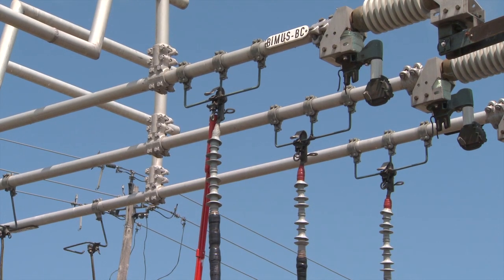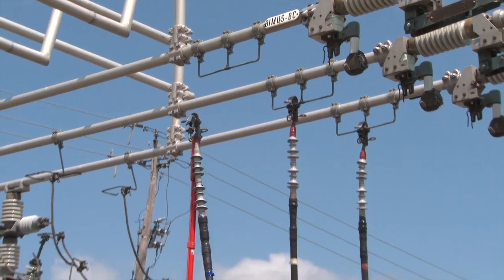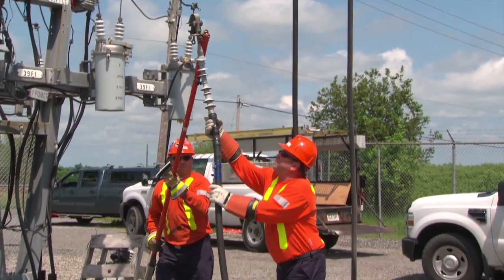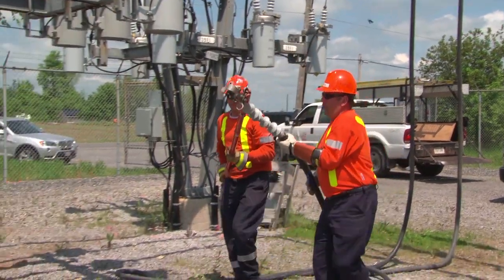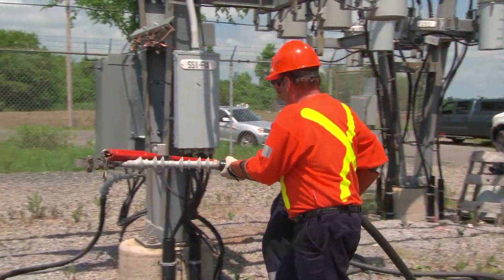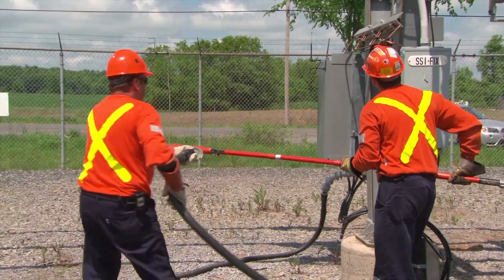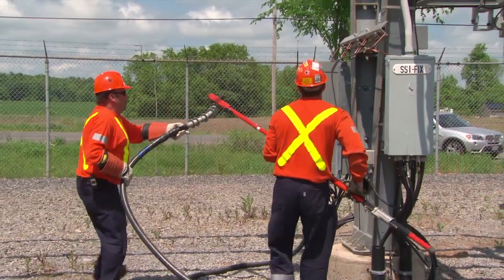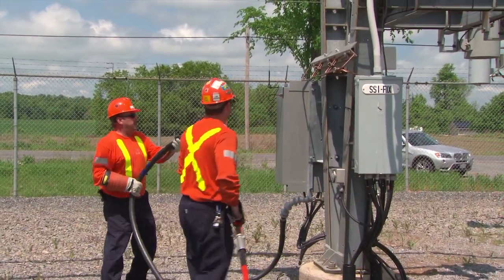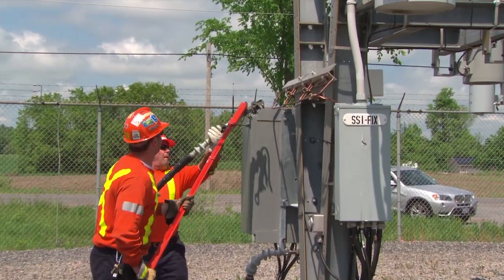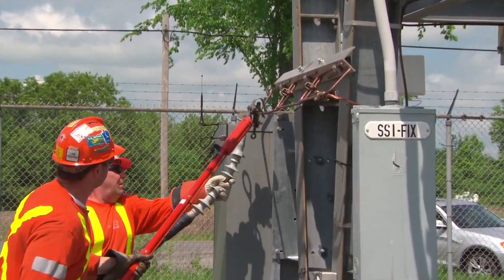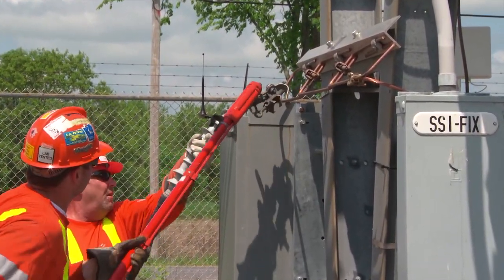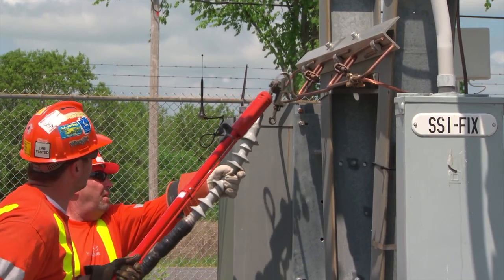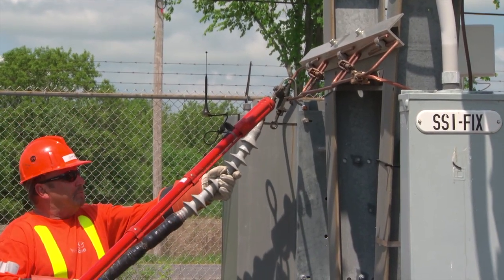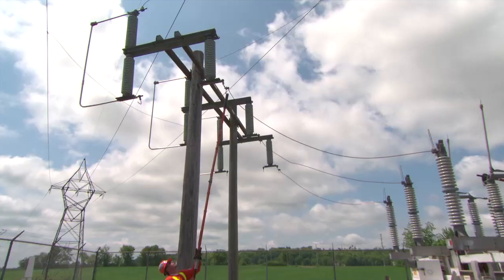When removing the cables, loosen the live line clamp and hook the grip-all onto the hardware ring fastened to the top of the cable. Don't take the weight of the cable using the live line clamp, because you could bend the clamp. Take the weight with the provided ring and control the descent of the cable to ground. Discharge the cables to the station ground or de-energizing stirrups. Do not use the fence to ground the cables.